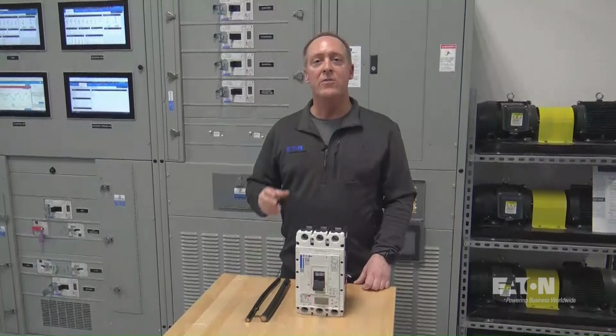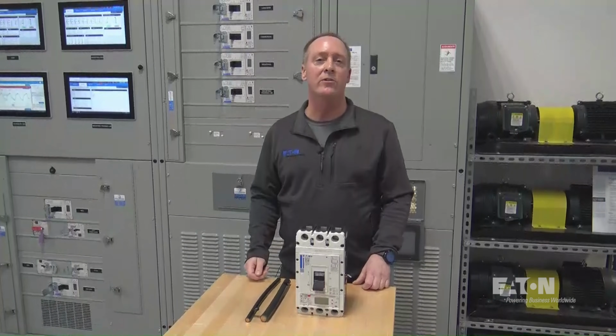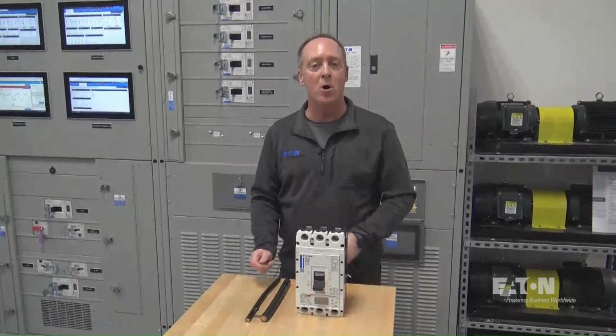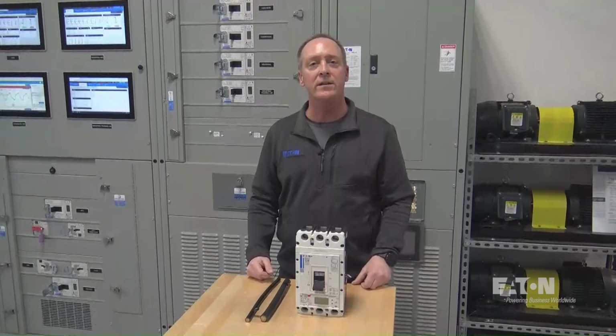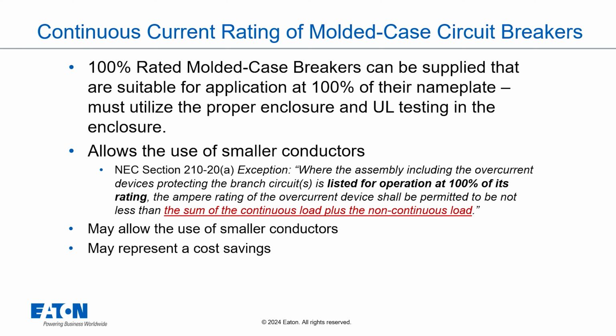cable. There is an exception in the National Electric Code for specific breakers that are marked and tested for 100% rating. In that case, the cables only have to be sized to 100% of the current continuous rating of the load. So for our same 100 amp load requirement, the cables would only be sized at 100 amps in this case, and then they could be applied onto a circuit breaker that was specifically 100% rated.